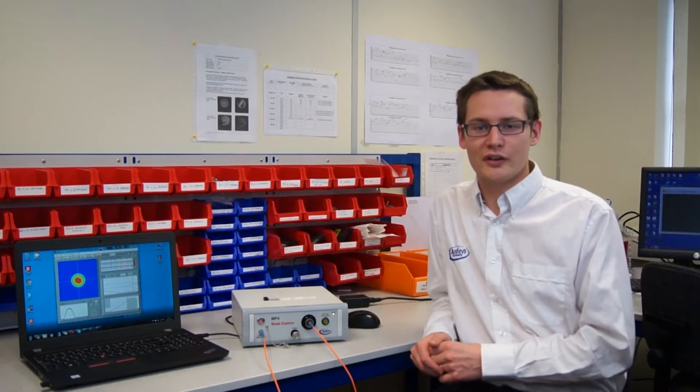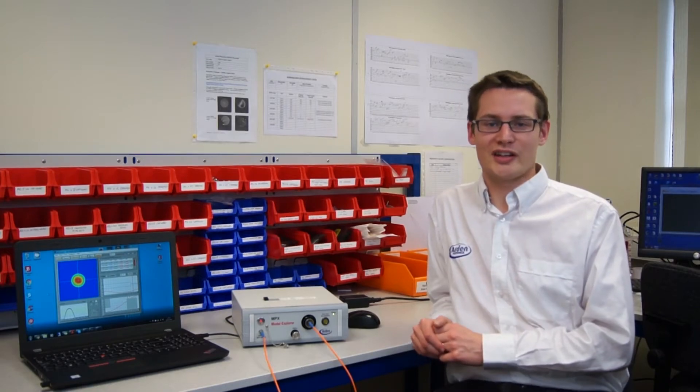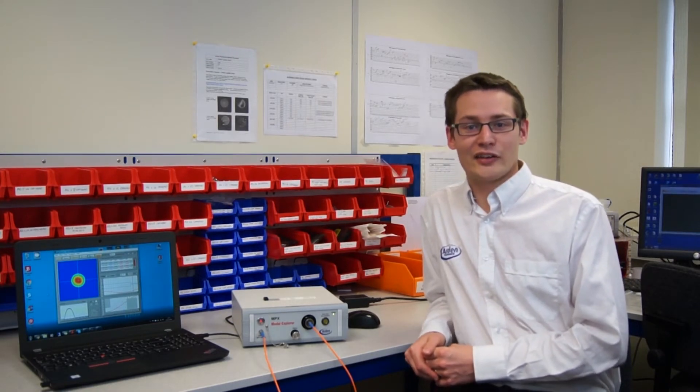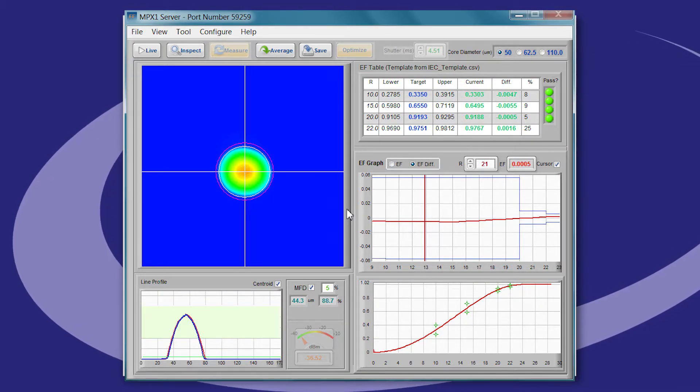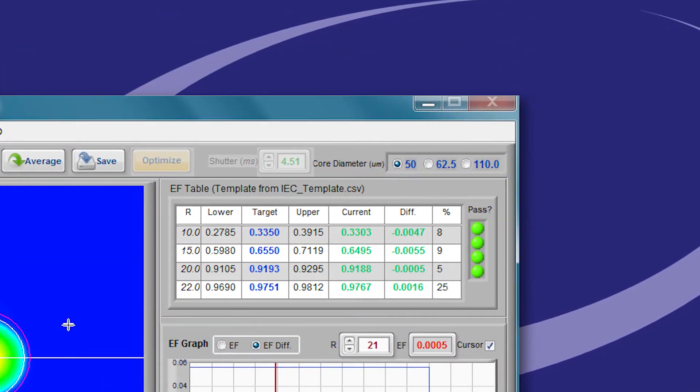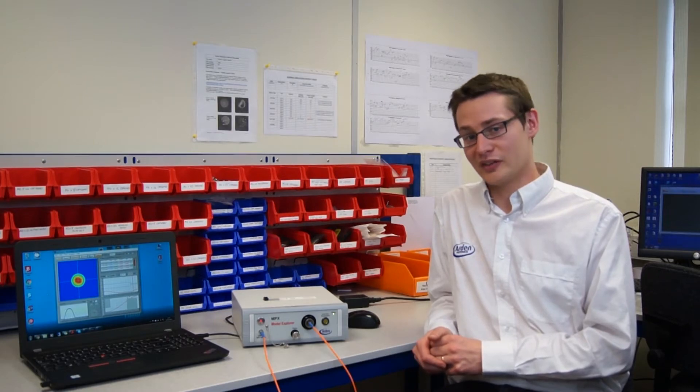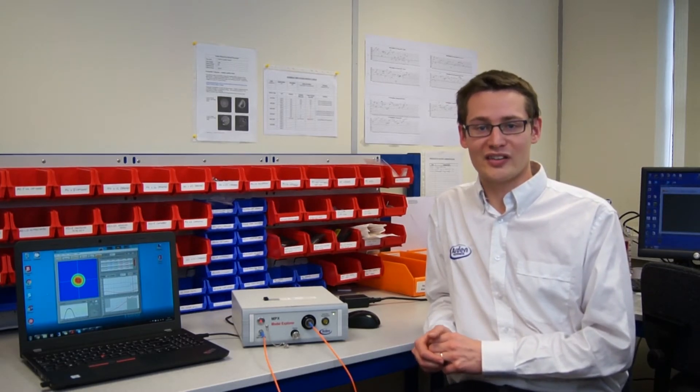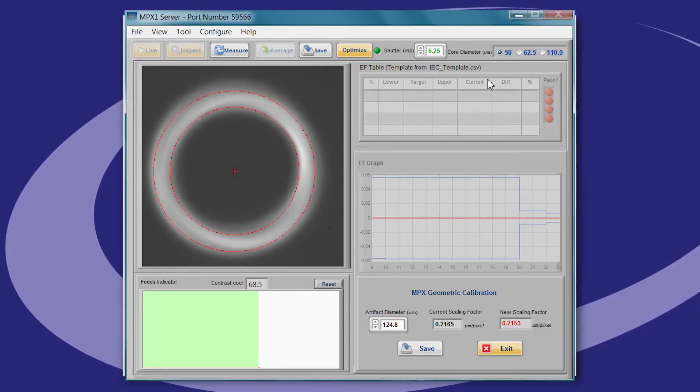The image window has also been increased in size by 16 percent. This has allowed us to increase the maximum core diameter size which can be measured up to 110 microns, and this is supported by the user definable templates. It also means that it's easier to calibrate the system using the optional calibration artifact.